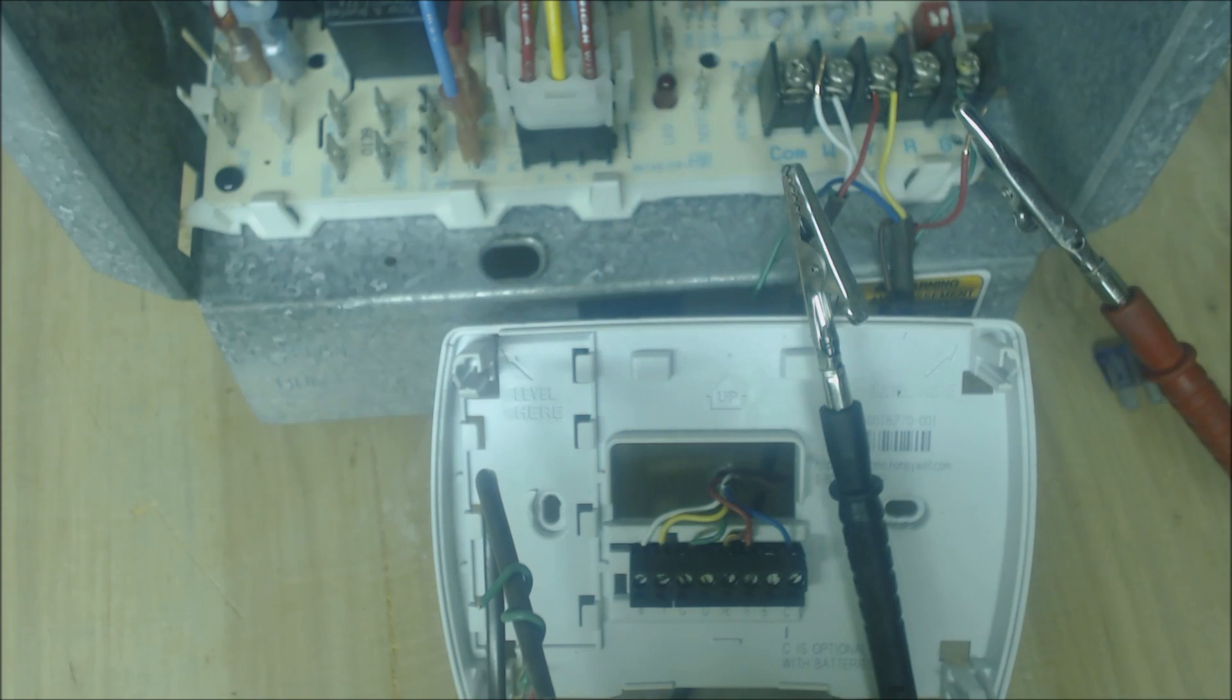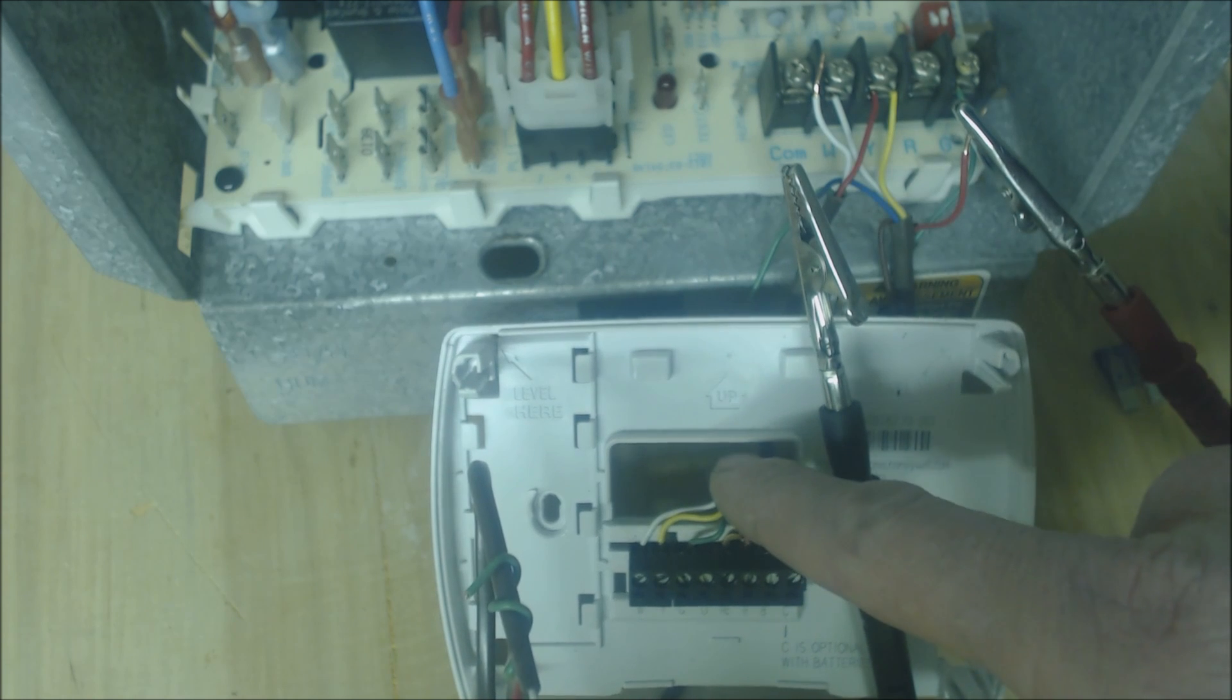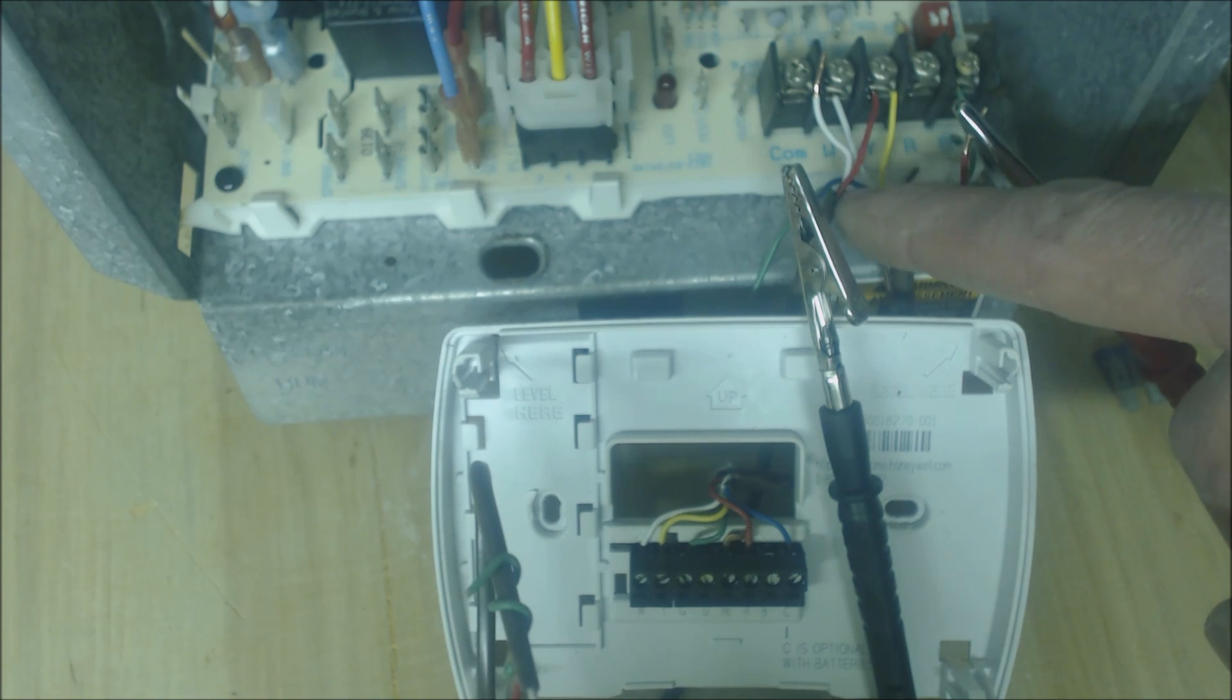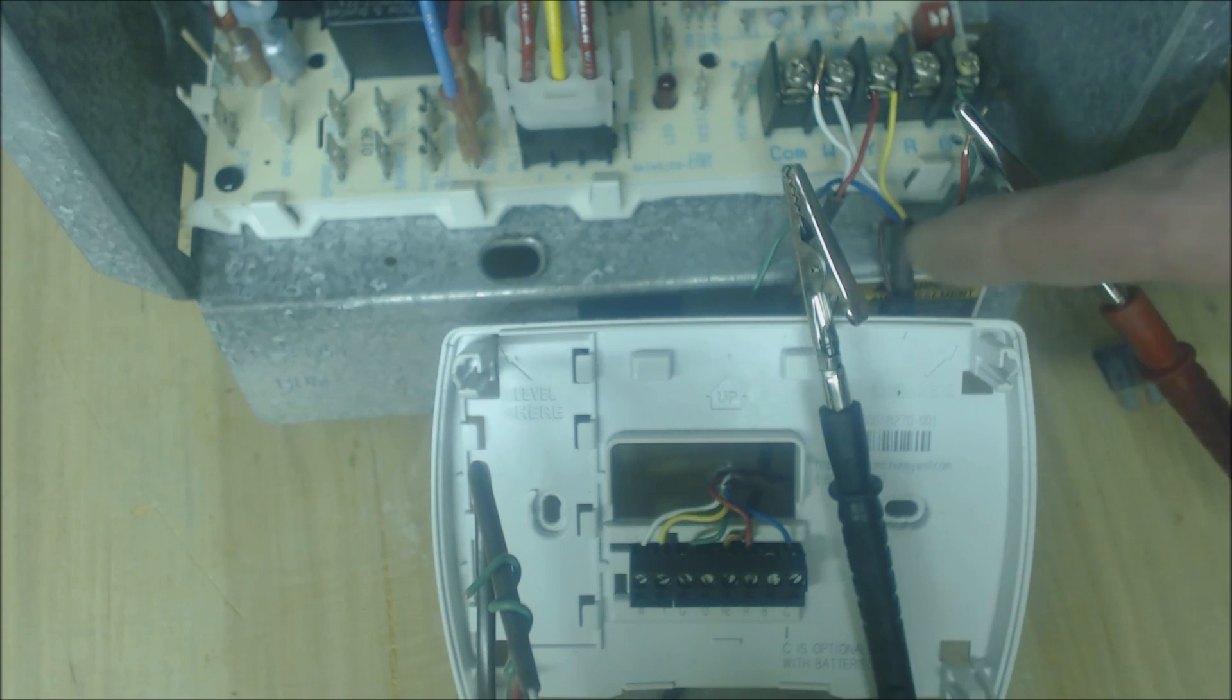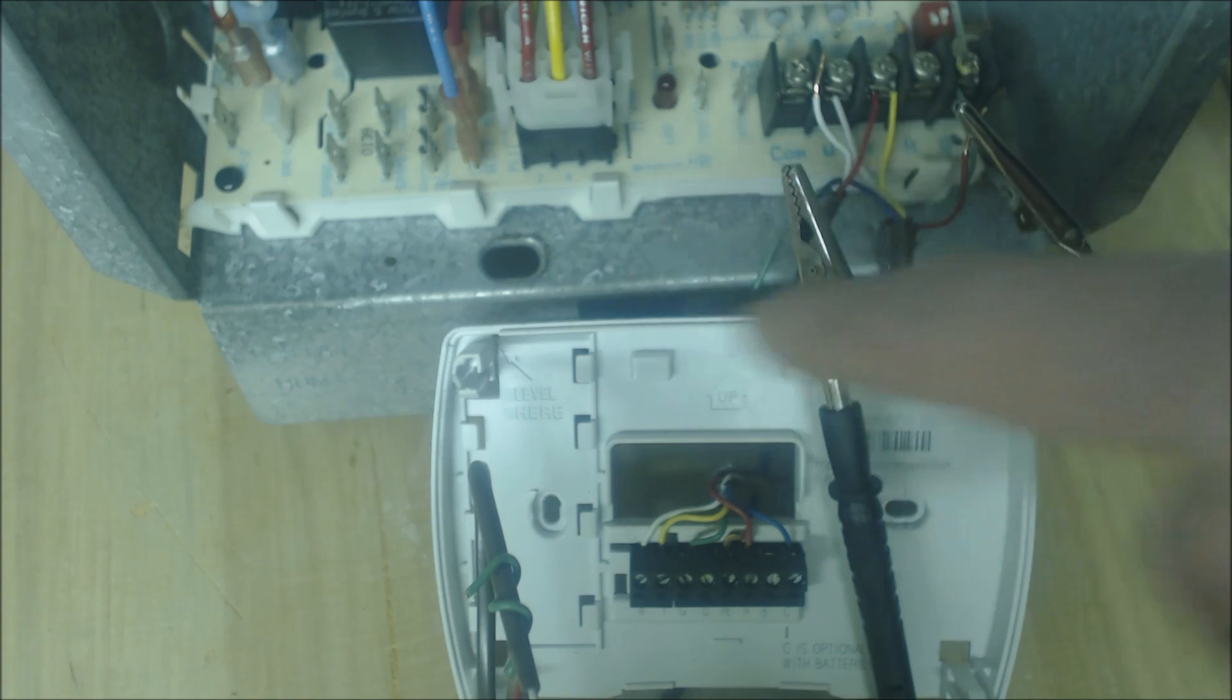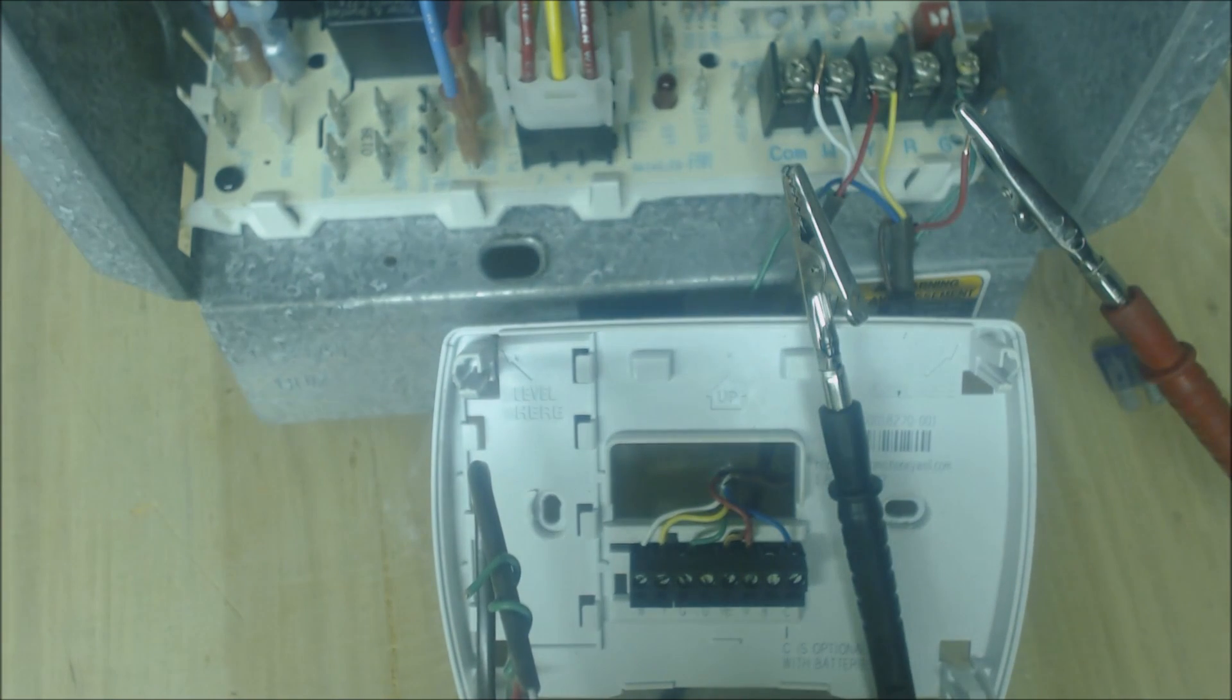It may be that somebody stripped the wires in here in a way where maybe they were cutting around the outside jacket, that brown wire, and nicked the wires. Maybe they're touching right there. That could be the issue, or somewhere along the line where the wall is or something like that. Maybe you got scraped, maybe there's a piece of metal, maybe where these thermostat wires are coming through the furnace or something along those lines.